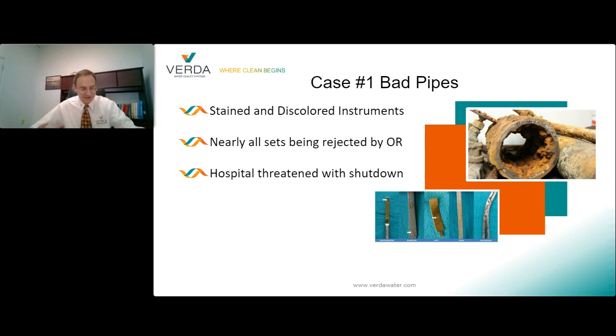So the problem fix was easy to state, but difficult to implement. Provide better quality steam feed water to the boilers. Great. But the boilers and the steam piping were designed for municipal grade water, not highly processed water. Like the city of Flint, their equipment was not designed to handle a water quality issue that they were experiencing. So the facility developed a short-term and a long-term solution.